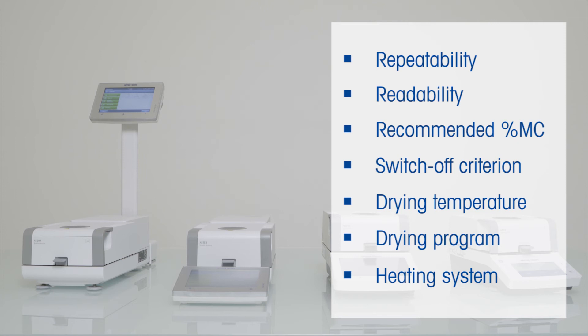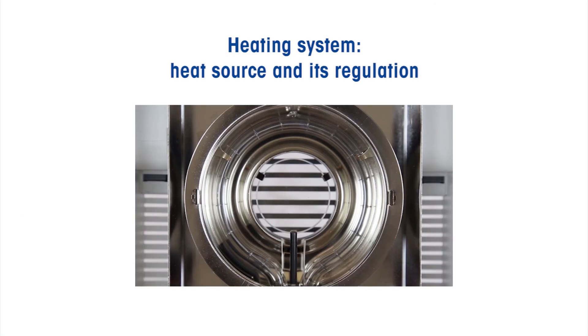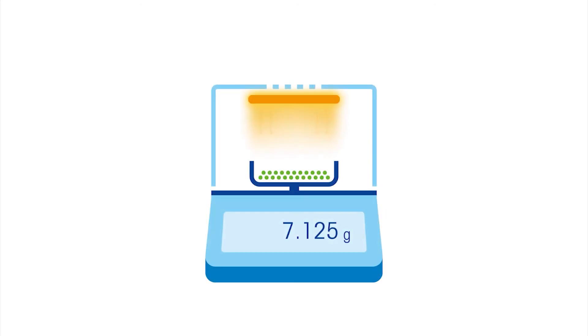The heating source together with its regulation are defined as heating system. In moisture analyzers, samples are usually heated by absorption of infrared radiation. Common sources of such radiation are halogen lamps, quartz lamps, and metal rods.